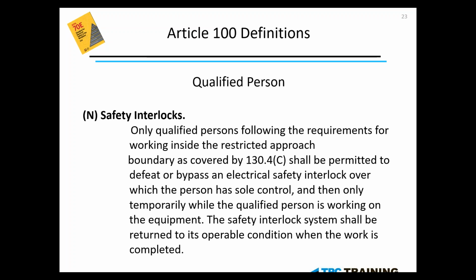Safety interlocks: only qualified persons may defeat or bypass a safety interlock temporarily. As soon as a qualified person is done working on a piece of equipment where a safety interlock was bypassed, they must or shall return it to its operable condition.